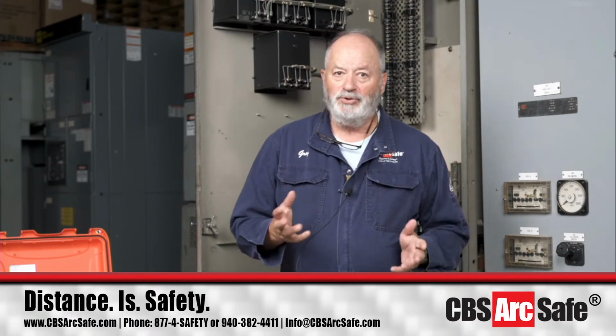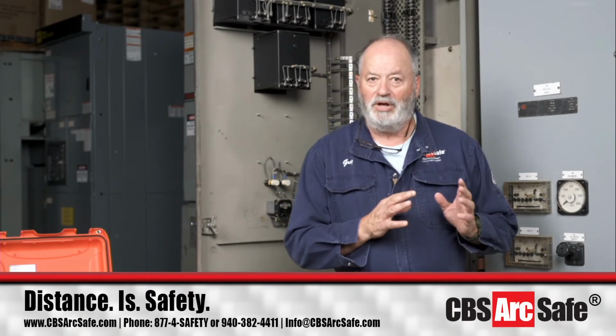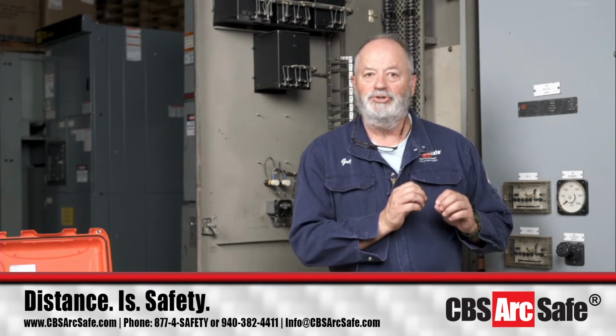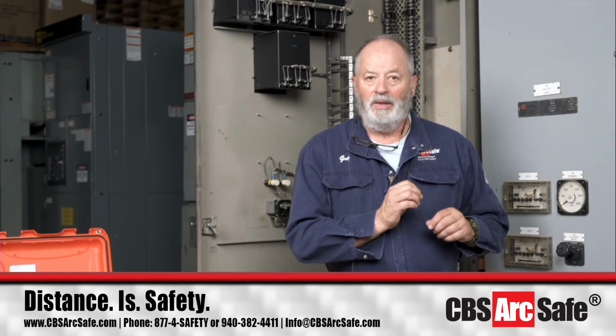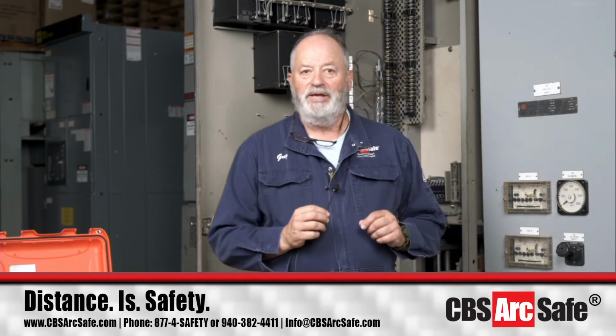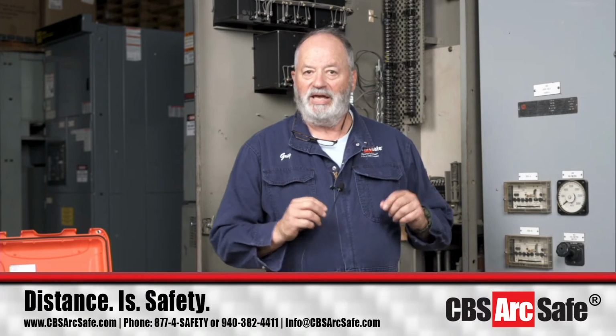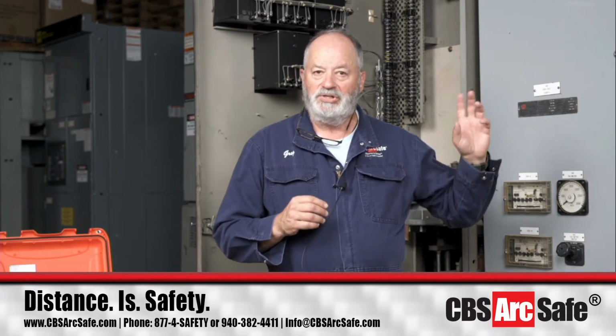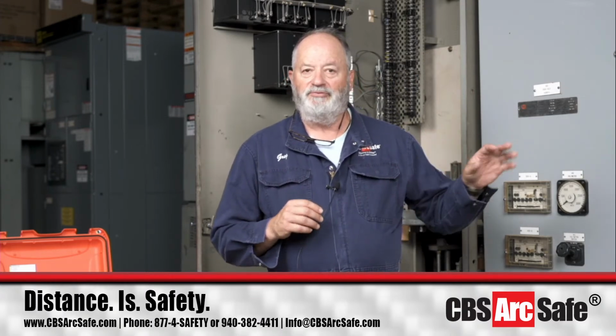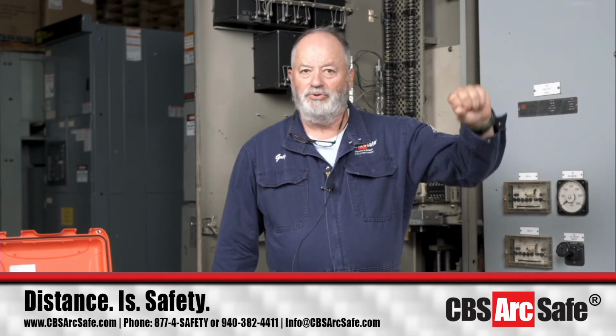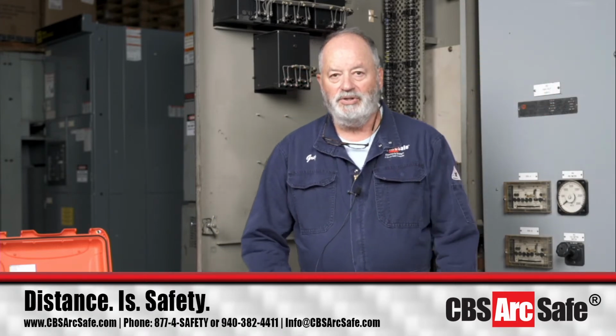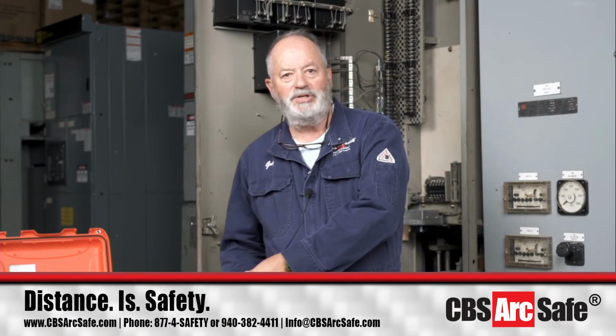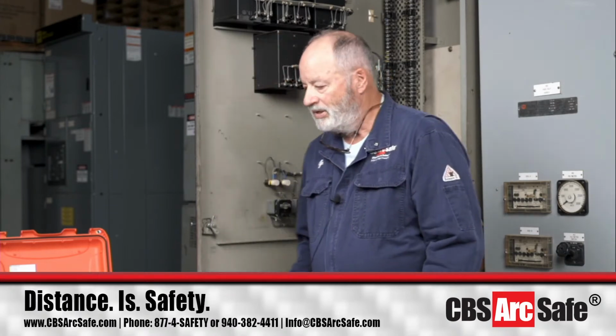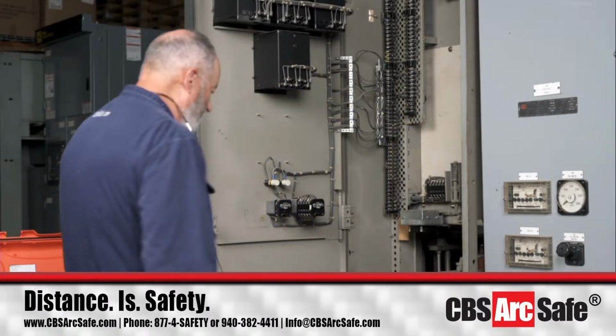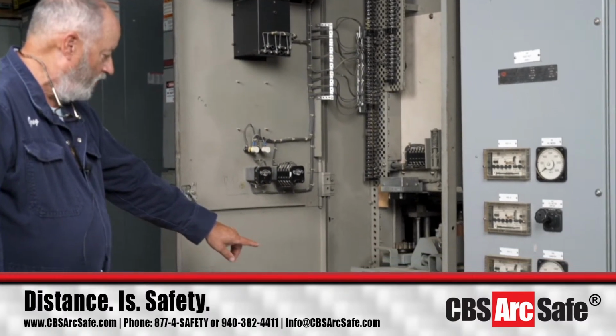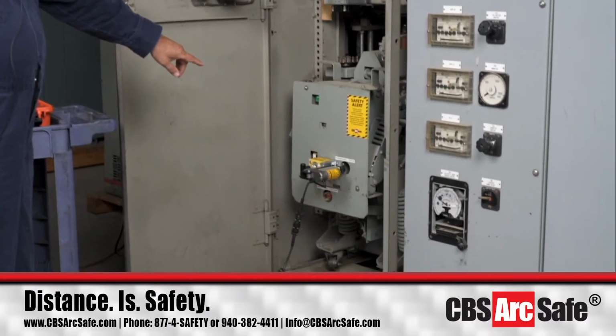Now, to start our actual demonstration today, the first thing I'm going to do is talk about our RS-01 and our RS-2 HD. We made this first for a power plant over in northern Louisiana because they had a peaker unit, and sometimes the SCADA gear wouldn't shut down from the control room, and then you'd go operate the control switch and the control switch might fail. So now you're going to the face of the breaker to shut this thing down. So instead of us using our standard little solenoid, which was not enough, we developed a high strength actuator that's going to be able to push.